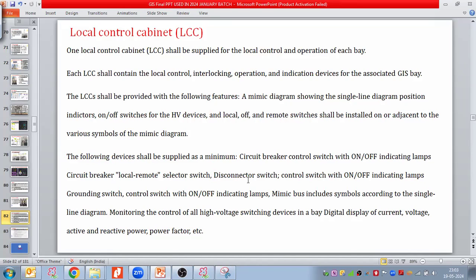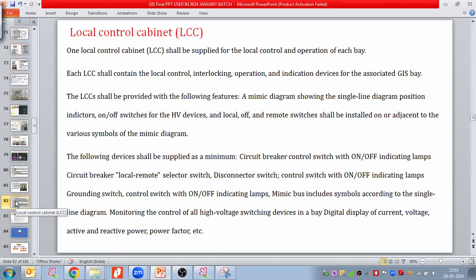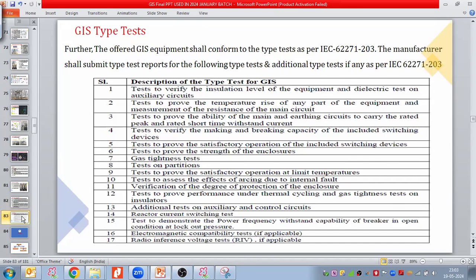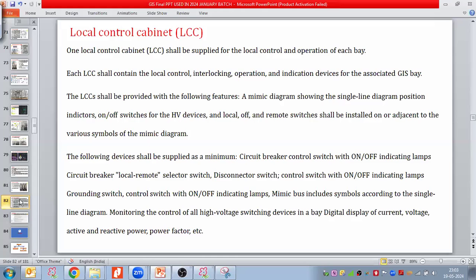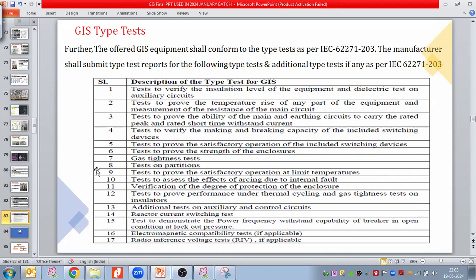Further, this local control cabinet is connected to the control and relay panel, the CRP panels. So all the cables from the LCC will go to the CRP panel, which we install in a separate control room. And this LCC we install in the same GIS hall in front of the GIS module.